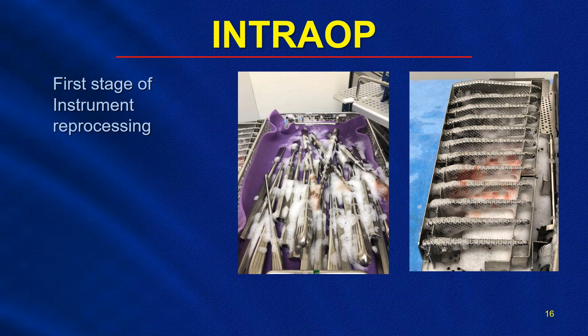And so the method of wiping down instruments and applying an enzymatic solution to them is known as point of use cleaning. Again, this is the beginning of the reprocessing phase. It happens in the operating room. If you look at the pictures here, you can actually see some of the blood on these instruments starting to come through on the foam. The enzyme in the humectant gel will break down the bioburden left on the surgical instruments from the procedure. Again, this is extremely important because if bioburden is left to dry on instruments, it may lead to the formation of biofilm. At that point, the OR will send these soiled and treated instruments down to central sterile for them to take over for reprocessing.